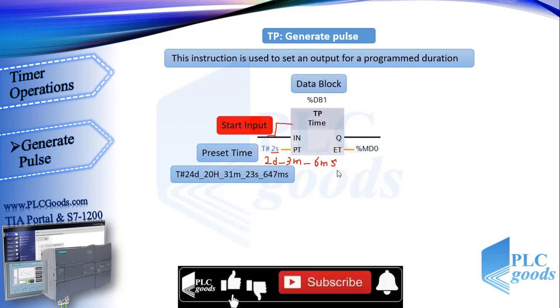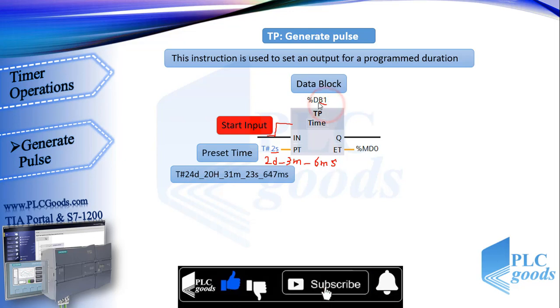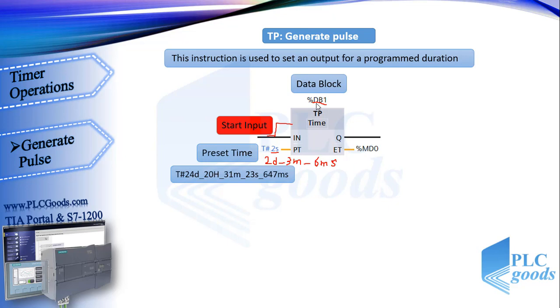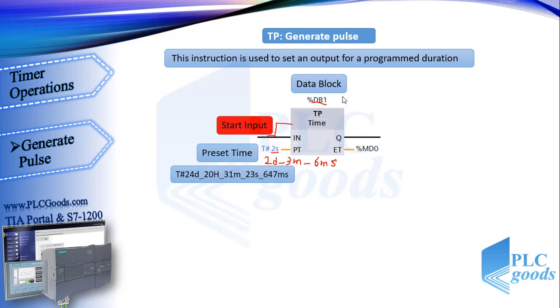Timers need a data block to work correctly, like some bit logic instructions which need a bit memory to work. Now what is data block? Data block is a block which stores the parameters of this timer. It stores the parameters like how much is the preset time and what is the status of the input and the status of outputs. So this data block is a memory which stores timer parameters and it makes that we can access this data in our program. So if you use another timer, we need another data block such as DB2 or DB3.